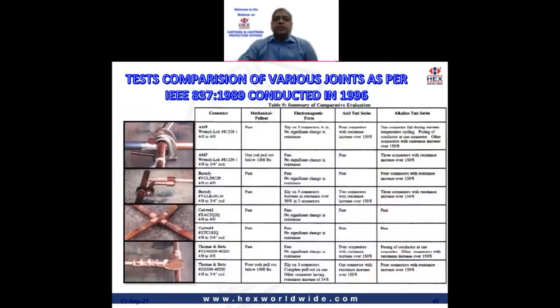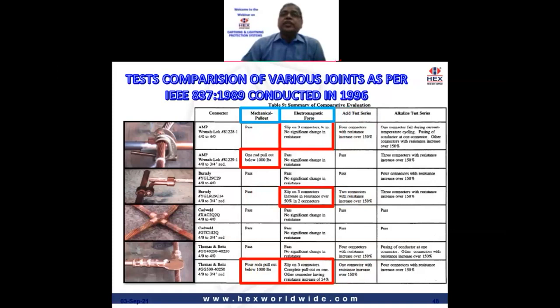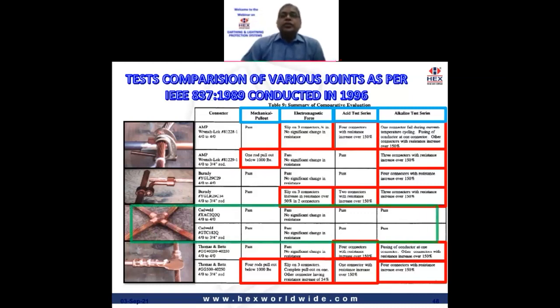Well, you can see, let us see the mechanical pullout test. One rod, that is the mechanical clamp, failed, and also a compression connector failed over there. Four rods failed there. Now, in the electromagnetic force test, again, three mechanical and six compression connections failed. Now, in the acid test, four mechanical and seven compression connections failed. And in the last test, that is the alkaline series test, 4 mechanical and 12 compression connections failed. But all the exothermic welded connections passed all the tests.